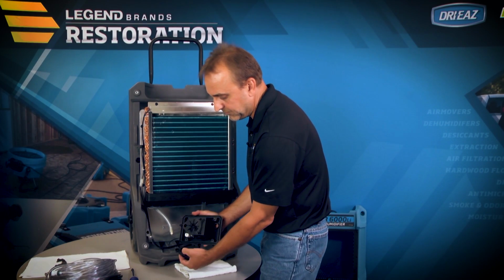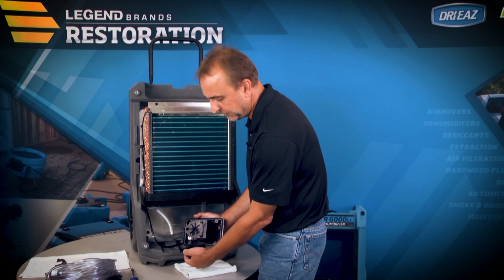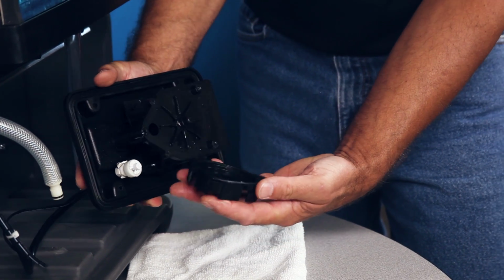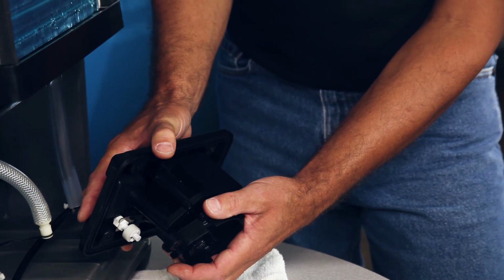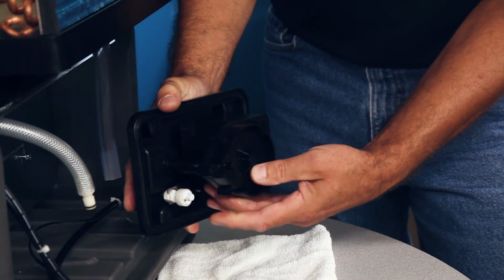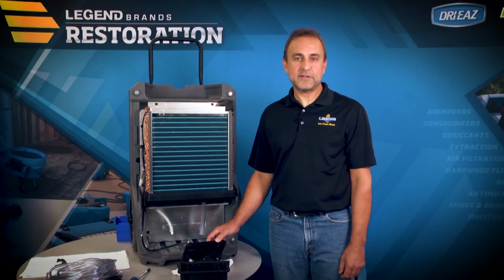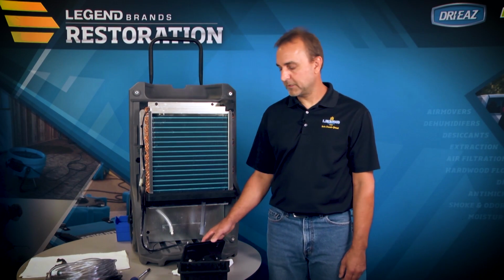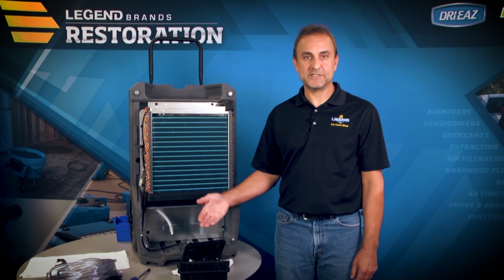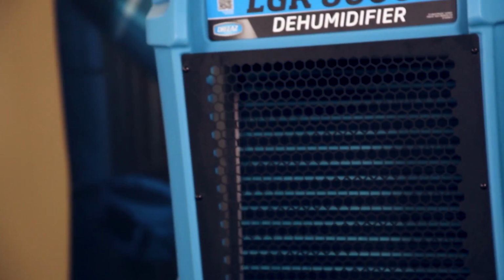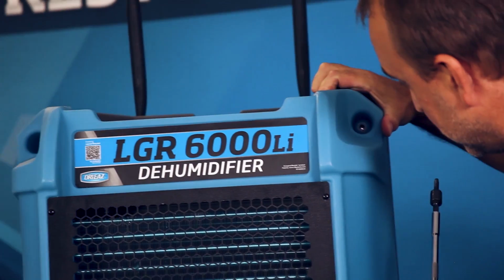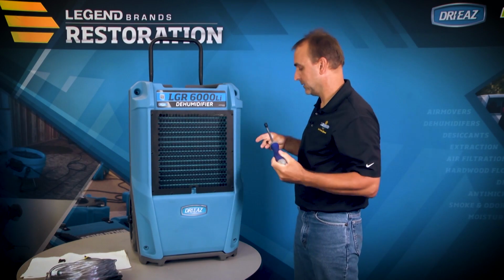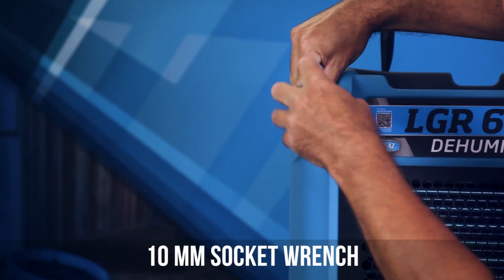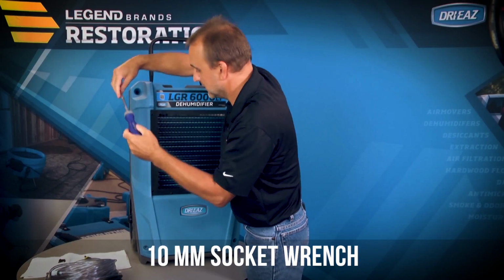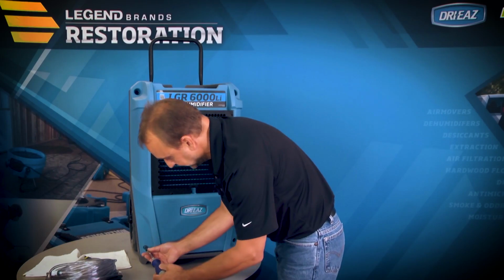Take your inlet cover, ensuring the diverter is pointing to the outer edge and the O-ring is in the groove, and reinstall it back on the condensate pump housing. That concludes the basic maintenance of the condensate pump. Follow the reverse steps to reassemble and install back in the unit. When reinstalling the front cover, make sure the housing is aligned with the insert. Start the top two fasteners, but don't tighten all the way. The bottom will be aligned, so you can tighten these down.